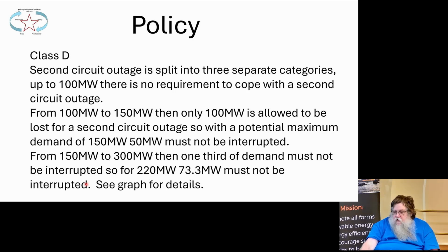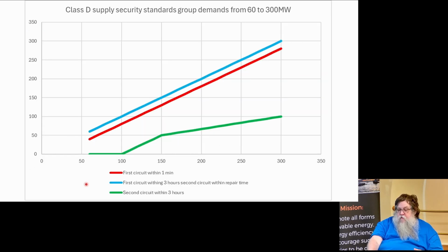Second circuit outages mean that if you've got a line out already and you get a fault, you can still maintain some supplies. If it's up to 100 megawatts, there's no requirement to maintain supplies, but then from 100 to 150 megawatts, you can lose only 100 megawatts. And then above 150 megawatts, it's 2/3. 1/3 of the demand must not be interrupted. So I've got a little graph here for it.